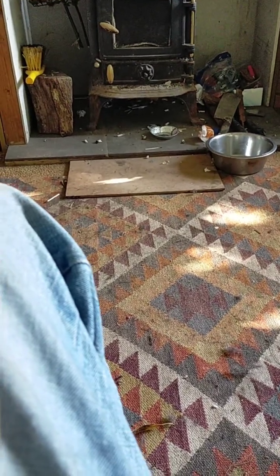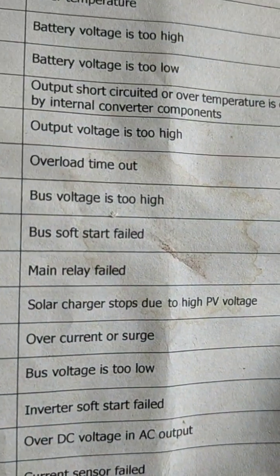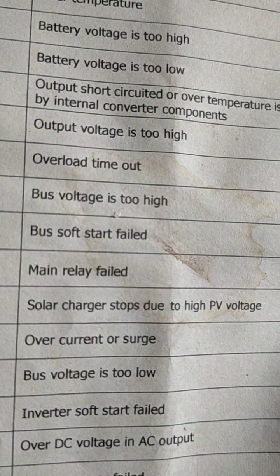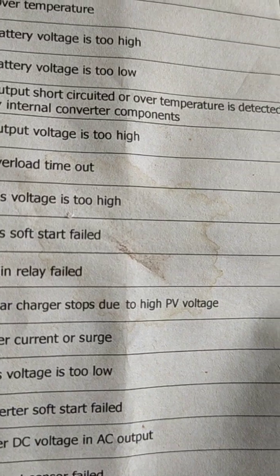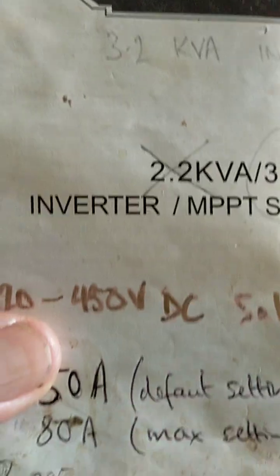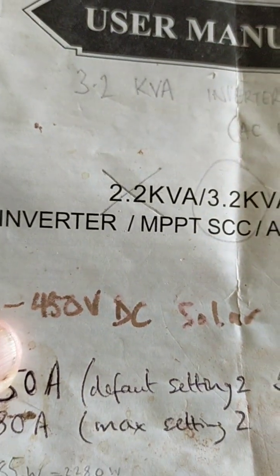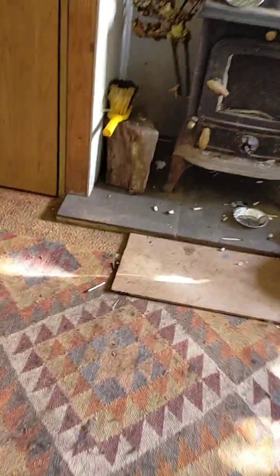Now it was reporting an error, which I'm about to uncover. This one, number 13, says solar charge stops due to high PV voltage. I looked at the front cover, it said the total PV voltage is 450 volts DC. So off we went to look at the machine, and I'm thinking to myself, 450 volts DC, crikey.